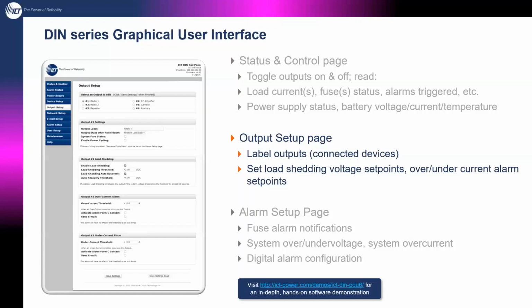On the output setup page, you can give names to each connected device. You can set the load shedding I mentioned before, where if you're on backup battery power and it's starting to drain, you set thresholds for certain devices to drop off - if the battery drops below a certain voltage, disconnect this device, and when power comes back and the battery charges, reconnect it. You can also set alarms for too much or too little current, define set points, and choose how you get those alarms, whether by text, email, and so on - very simple and easy.